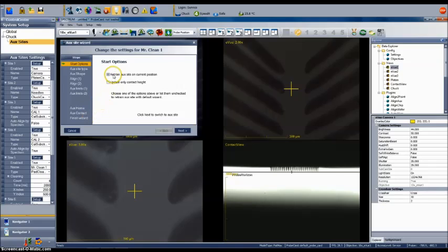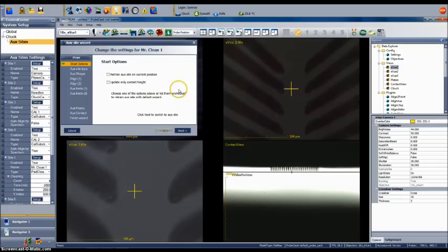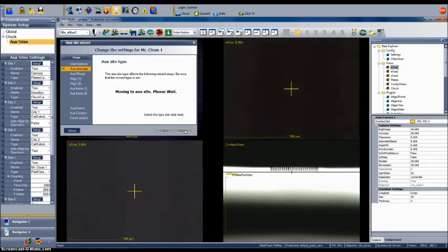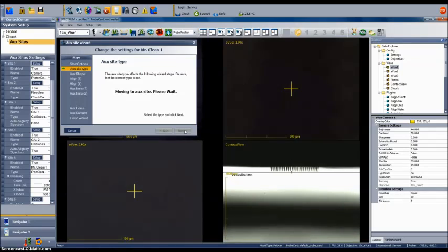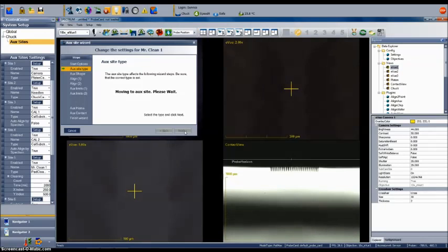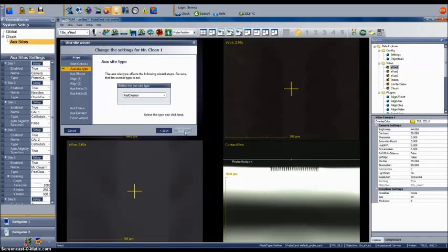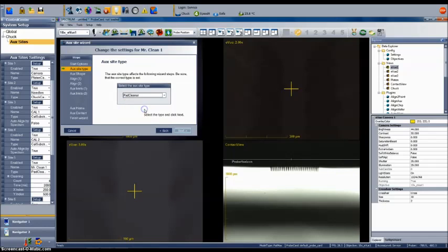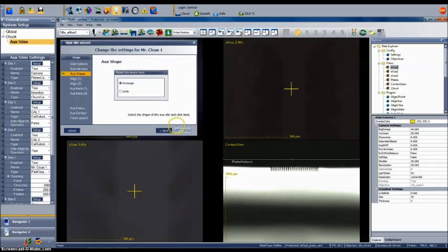At the beginning of the wizard, there are a few options. You can retrain the aux site on the current position, update only the contact height, or leave all options unchecked to completely retrain all settings for the pad. I will go with this choice. Select Next and then select the type of pad being installed. In this case, select Pad Cleaner and then select Next. Next choose the shape of the pad and then select Next again.